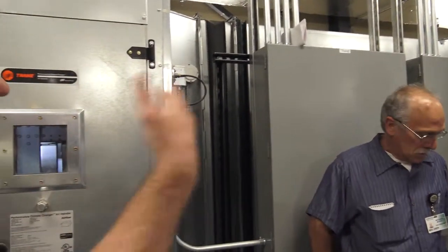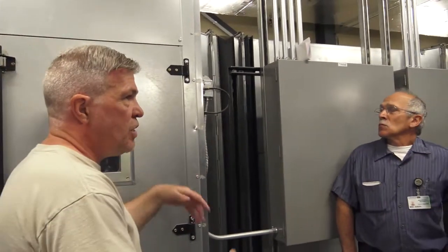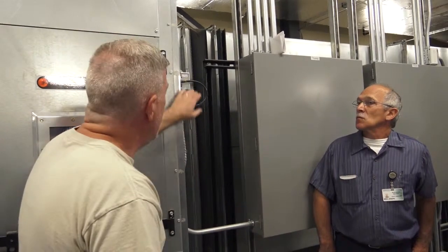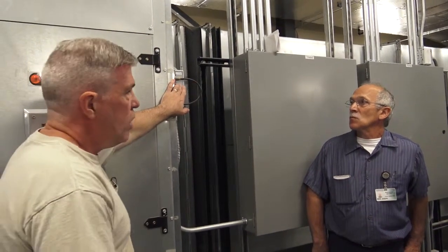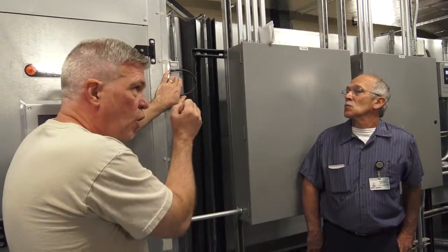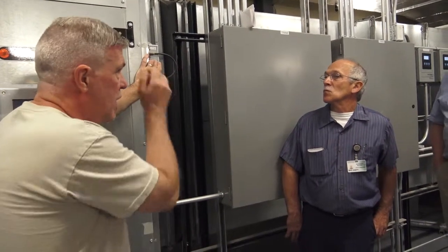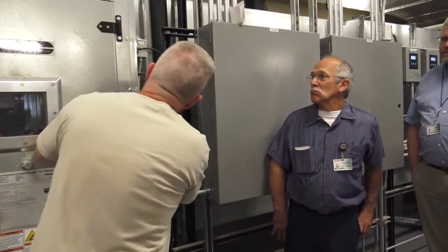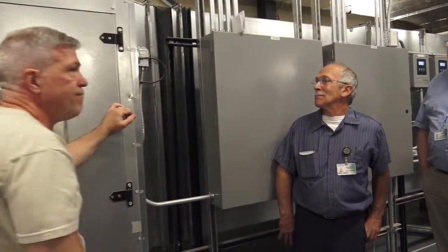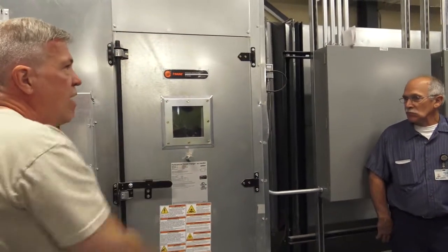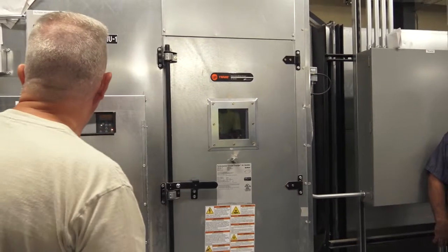So for some reason you got a fire smoke damper, something that closes, that causes your duct pressure to jump real quick. This will trip out and shut the unit down too. But again, it'll trigger one of those relays will go off, and you'll also get an alarm that says your high limit's tripped. So resetting on this is pushing the white button. Same thing you have on a lot of the other ones, but that's where it's located.